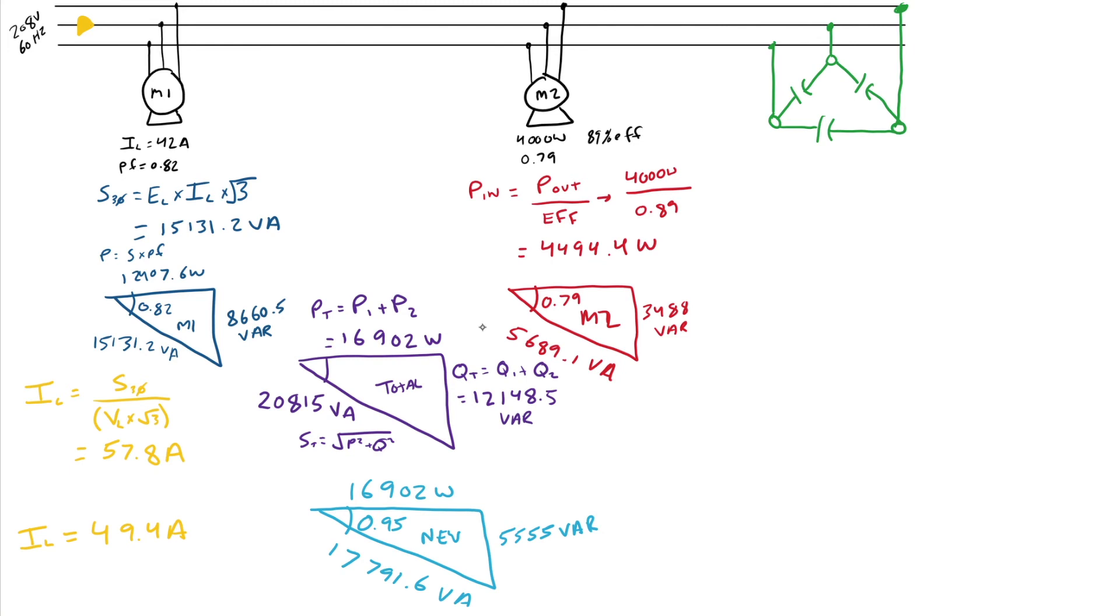Now what I want to do with that information is I want to size my cap bank size. So I take my original VARs, 12,148.5 VARs. And I subtract my new VARs, 5,555 VARs. What I get, the difference between them is the size that my capacitor bank needs to be. So in this case, I get a size of 6,593 VARs.